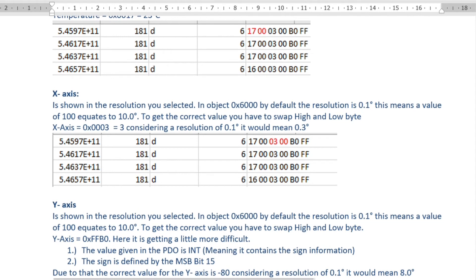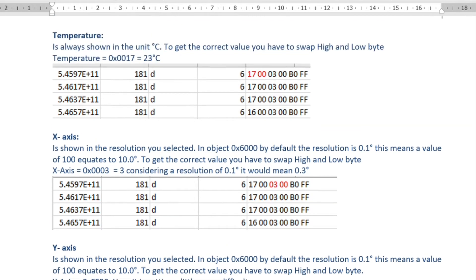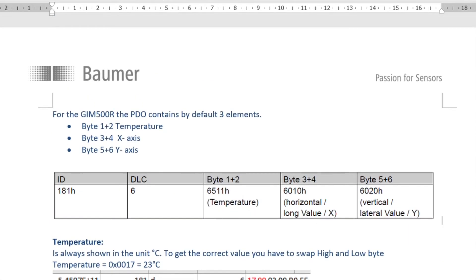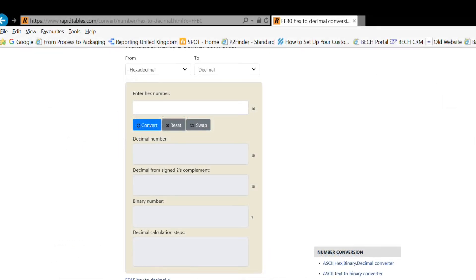I hope that helps explain how you decode the information. It's standard CANopen protocol — you just have to perform the high-to-low byte swapping in your PLC or whichever control method you're using, and then decode from hex to decimal to give you the answer. So: the first two bytes are temperature, bytes three and four are the X-axis, and bytes five and six are the Y-axis.